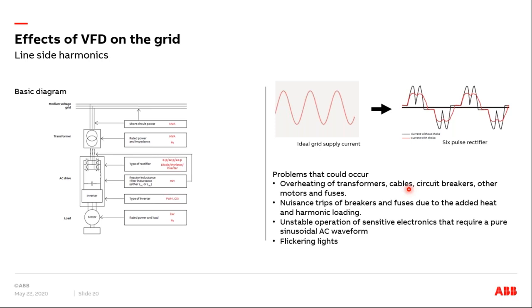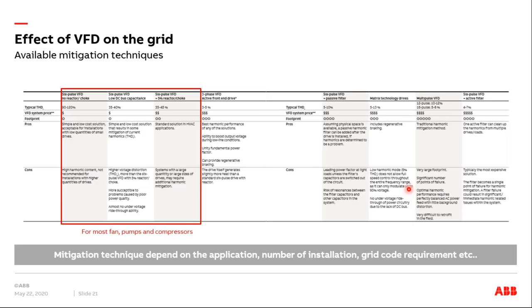So there are two phenomena. One is the I square R losses, because you are adding harmonics, and if this is 90% harmonics, your I square R increases and the losses increase a lot. It's like a 90% overload, which is bad. If there's no mitigation, it's a lot of load on your transformer. For example, in an industry with 100 VFDs rated at a megawatt total, you are loading your transformer to almost two times. If that transformer was rated at 1 megawatt to serve that industry, the real load will be almost two times that.